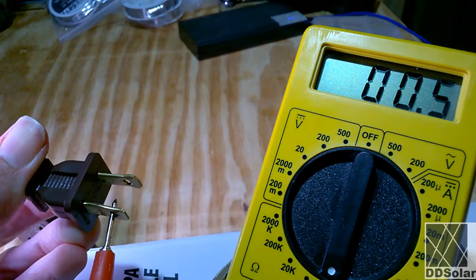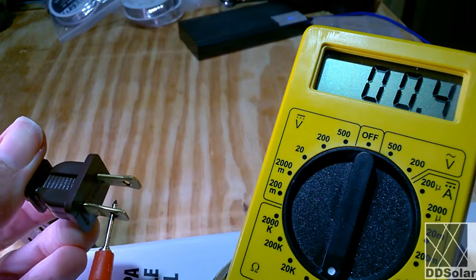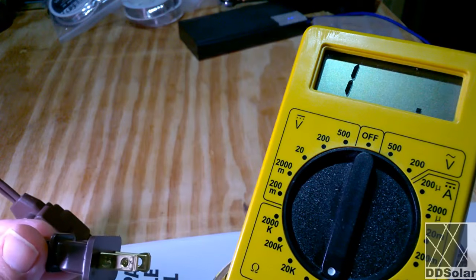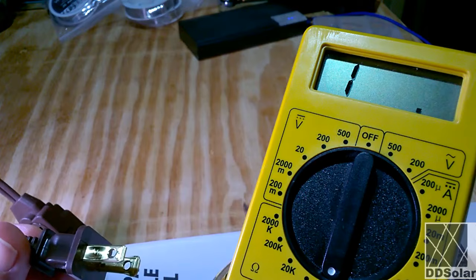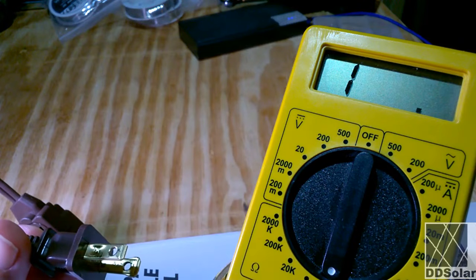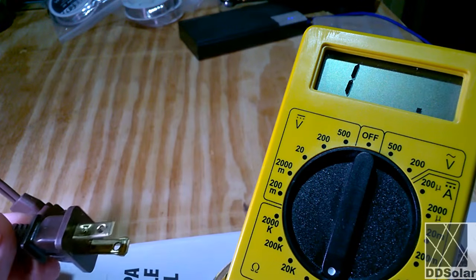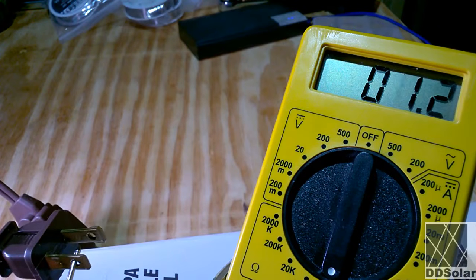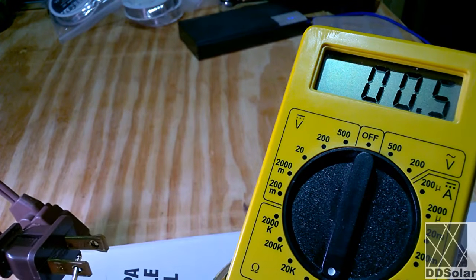And sometimes you have to wait a while for the reading to settle down. In this case, it takes a while. So effectively, this cord has a very low resistance, as I expect. I don't want to see like 3 ohms or 5 ohms on a cord like this. It's about 20 feet long. 5 ohms would be very, very high, and that cord, it's either a bad cord or it's going to get really hot in operation, and I wouldn't use it for anything important, or possibly even just throw it away. But this cord is fine, and 0.1 of an ohm or 1/10 of an ohm is very small and is nothing to be concerned about.